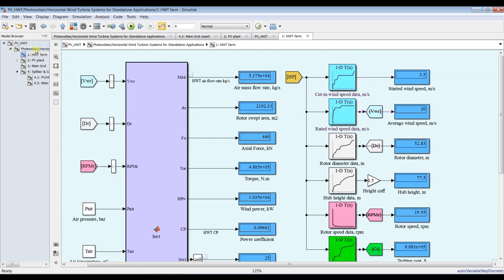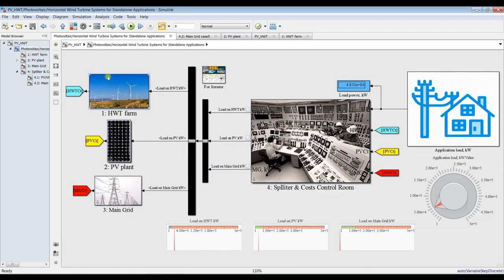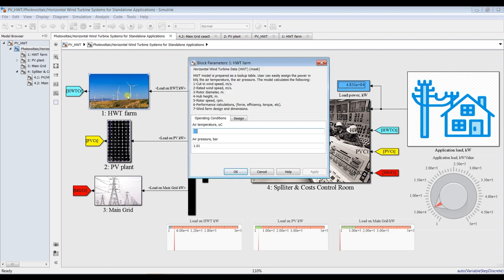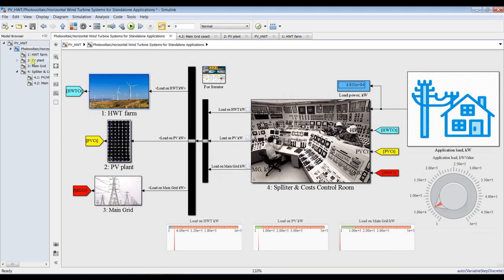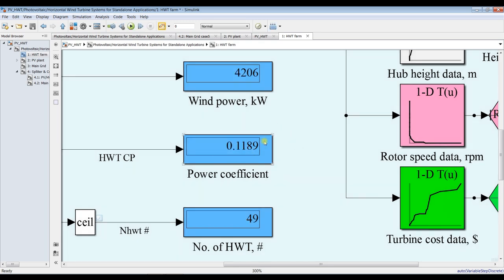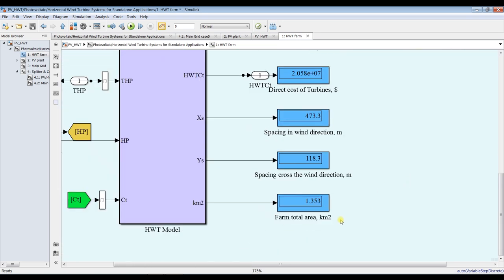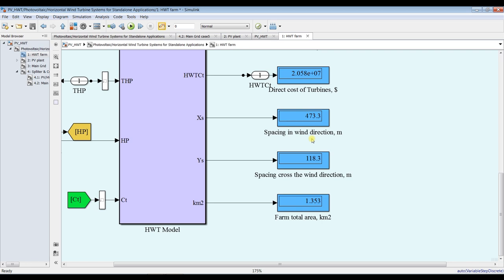I need to increase the power coefficient of the turbine, so I need to choose a lower module. It will increase the cost, but let's go for the 500 kilowatt module and see if we can increase the power coefficient. Let's hit run. The power coefficient has increased, but the number of turbines has increased too, and so has the total cost. It depends on your optimization or design requirements.